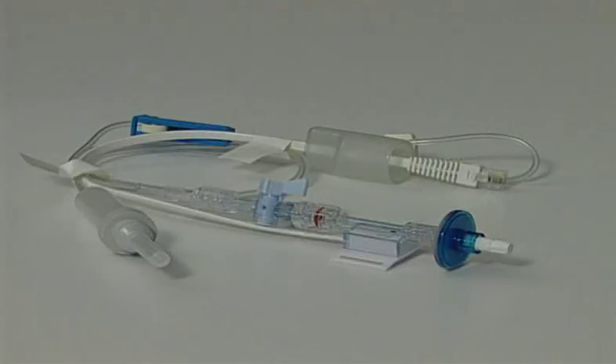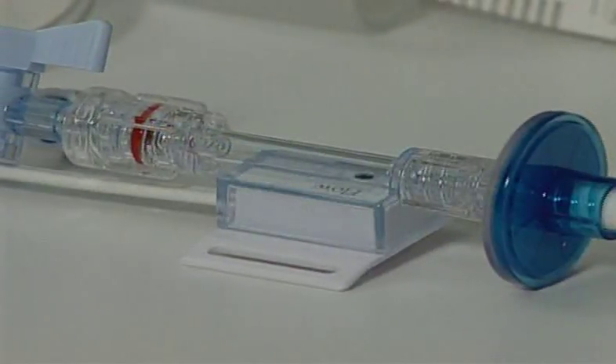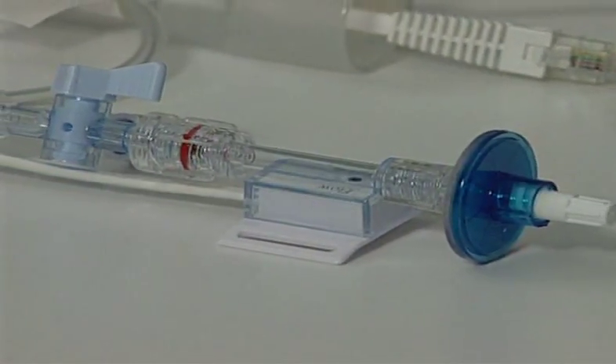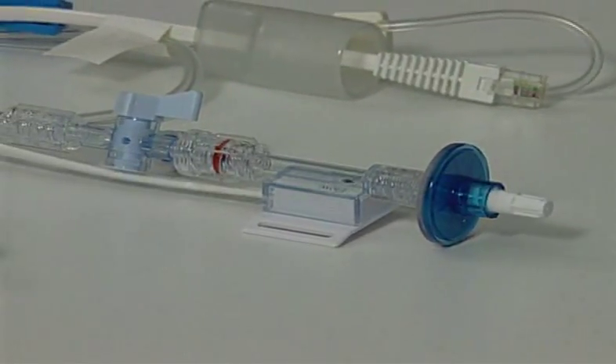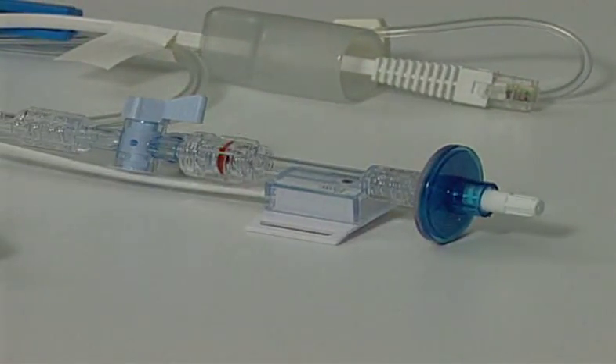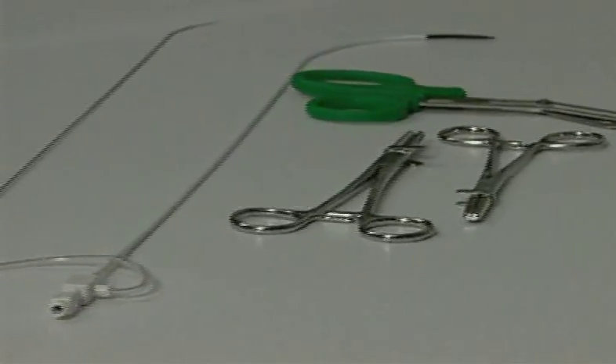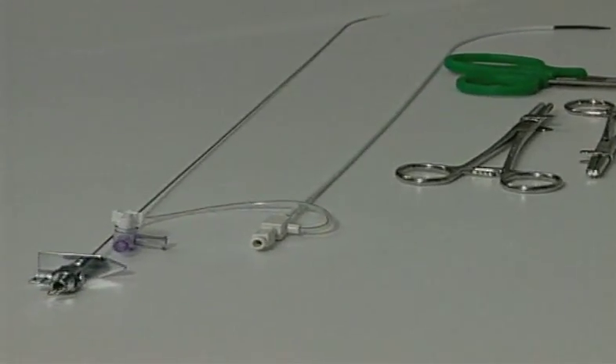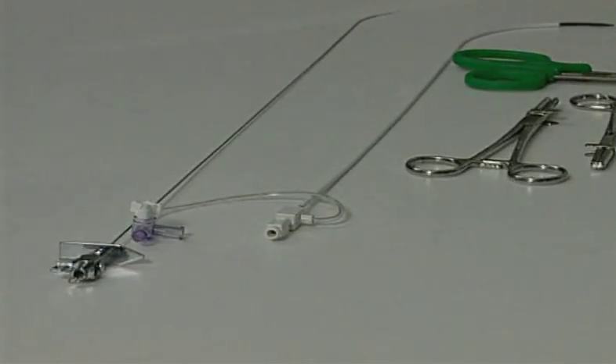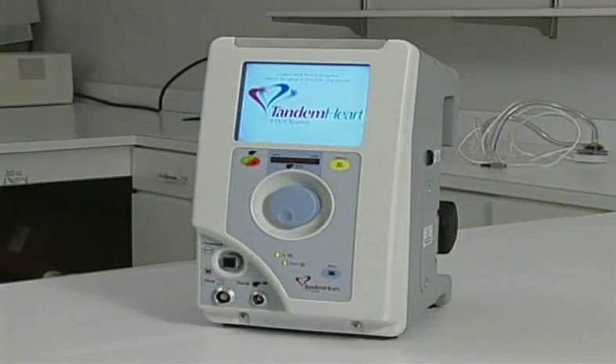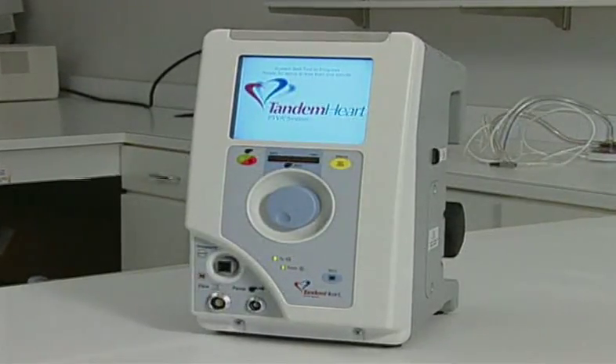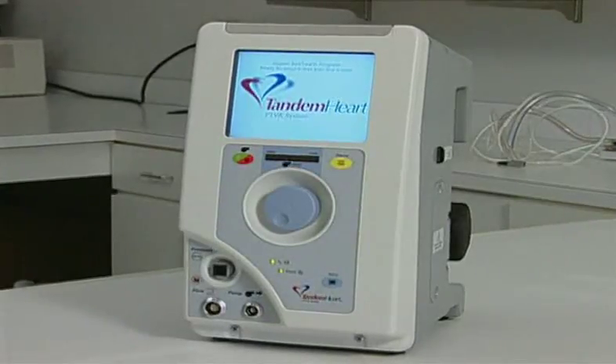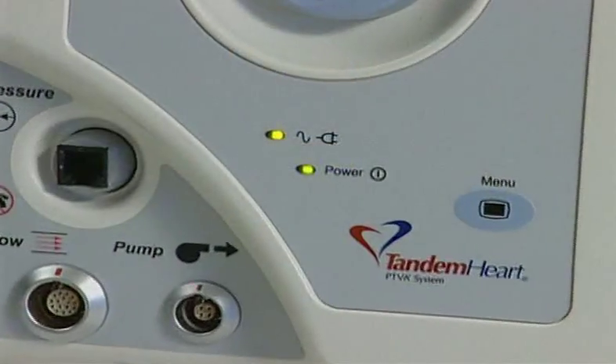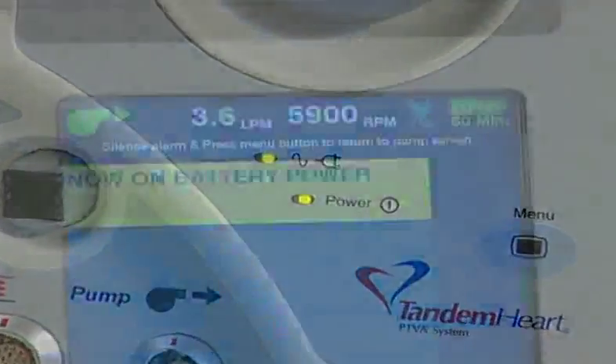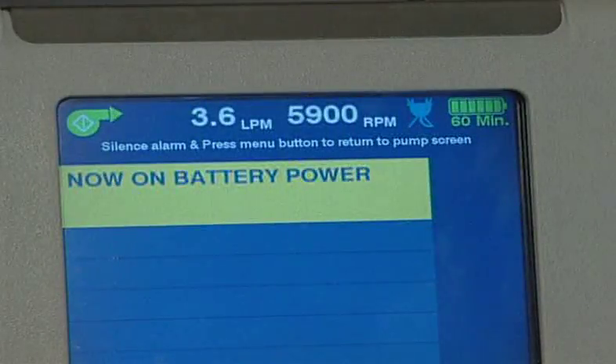The Infusate tubing set comes pre-connected with a bacteriologic filter, stopcock, and pressure transducer that monitors the Infusate pressure in the TandemHeart pump. Hospital-supplied items include tubing clamps, scissors, and transseptal access supplies. The TandemHeart Escort controller powers the system, provides diagnostic alarms during operation, and flow measurement. It operates on AC current and also has internal batteries to provide 60 minutes of continuous operation during patient transport.